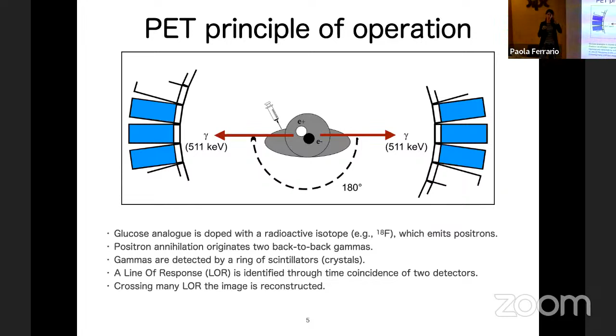Usually, these detectors are crystals, scintillators, so they respond to the arrival of the photons with light. So one detects light, and this is the way we draw all these lines of response. One of the figures of merit of a PET scanner, so to say how good a technology is for PET scanners, is the concept of sensitivity, which is basically the number of coincidences of these 2 photons that are detected by the device per unit time and per unit of activity of the source that is injected. So the higher the sensitivity, the better your PET scanner.